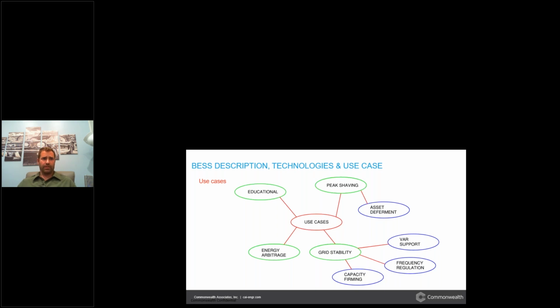Peak shaving is a similar concept. When the demand is high, some equipment in the overall electrical network might be slightly overloaded. So peak shaving with BESS near the load might prevent the case of an overload on some pieces of equipment and overhead line, potentially. So some are using this specifically to push a substation major equipment replacement into the future, just so that planning can be done. If there's only like an hour or two a day that, say, a transformer is overloaded, and the BESS can be there lending a helping hand, that's being used for asset deferment.